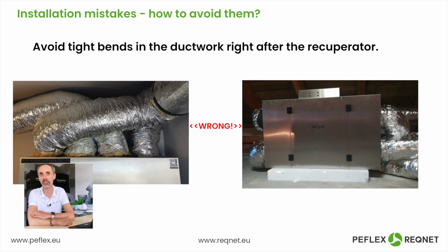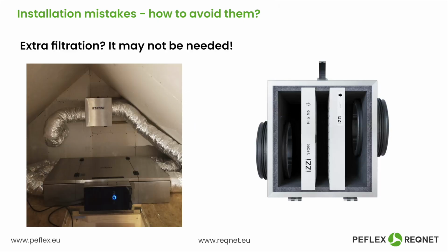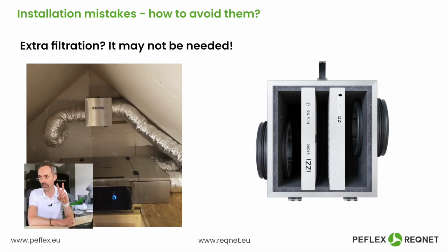Fans have their own limitations when it comes to resistance and output. Maybe it's not such a big mistake, but in the Reqnet series ventilation units, we have 2 filter inlets, so an additional box. If the filters are not removed from the heat recovery unit, it will create extra resistance, which means we might once again fail to achieve the desired performance.